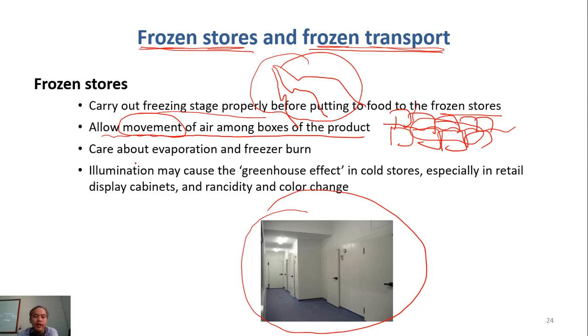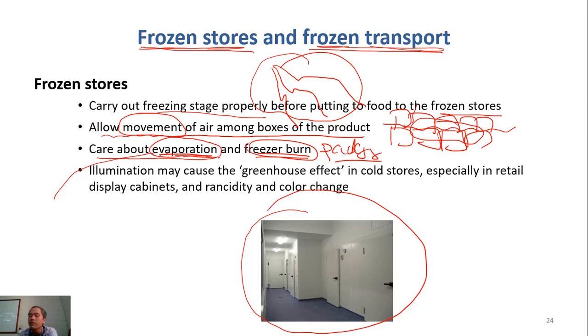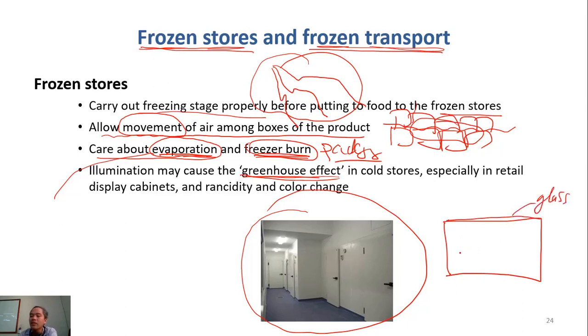We also try to limit evaporation and freezer burn. To prevent freezer burn, we need proper packaging. The cause of freezer burn is sublimation — the conversion from ice directly to vapor — and if you lose water over a long term, you will have freezer burn. We also need to be careful of the greenhouse effect, which normally occurs in supermarkets where food is placed in a freezer with a glass cover so customers can see the product inside.